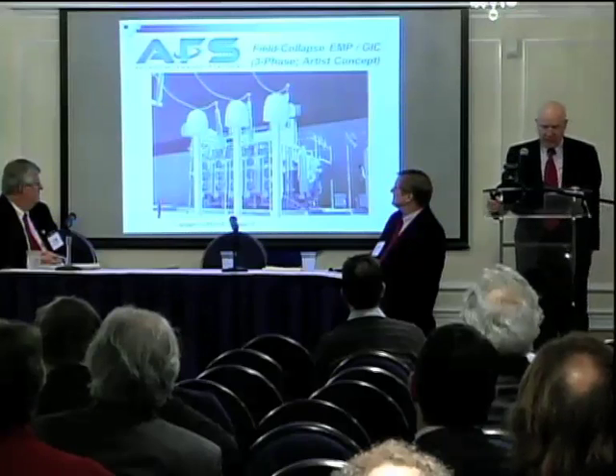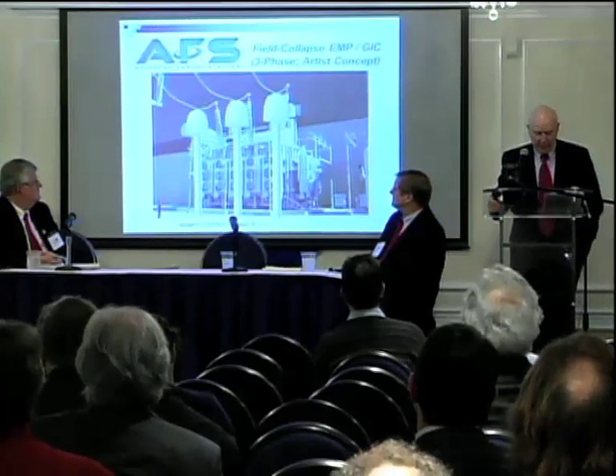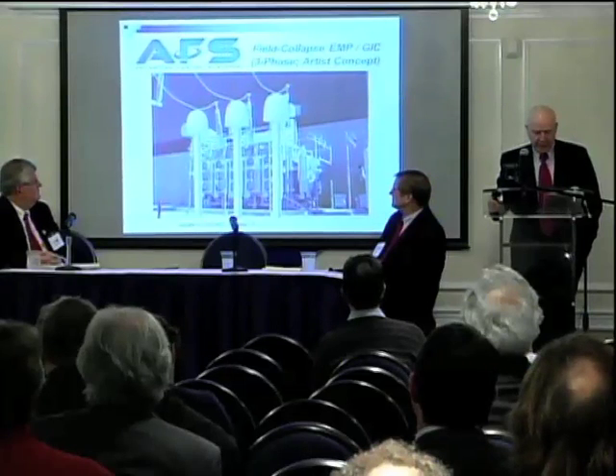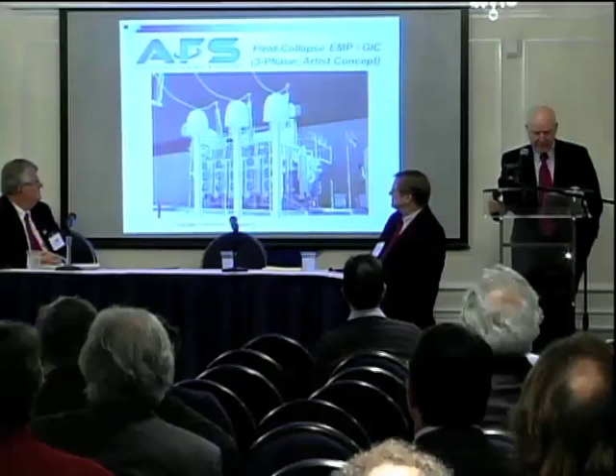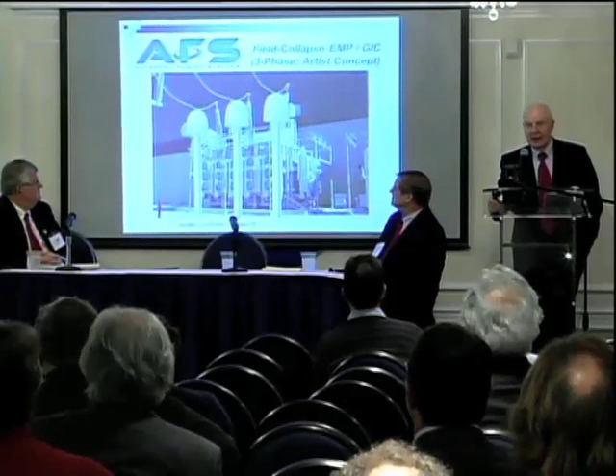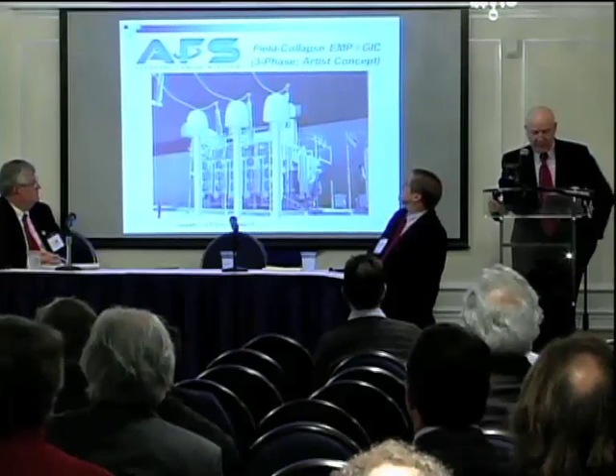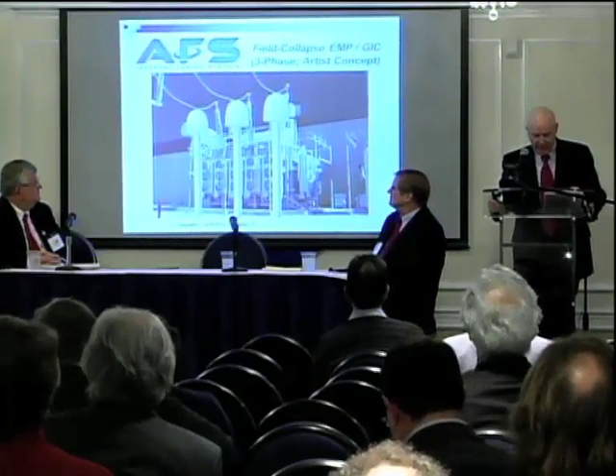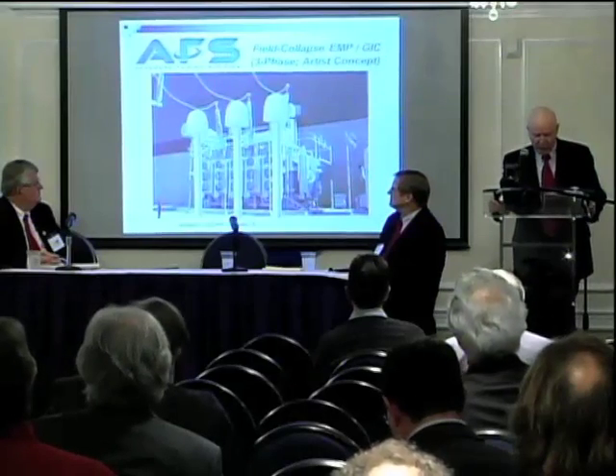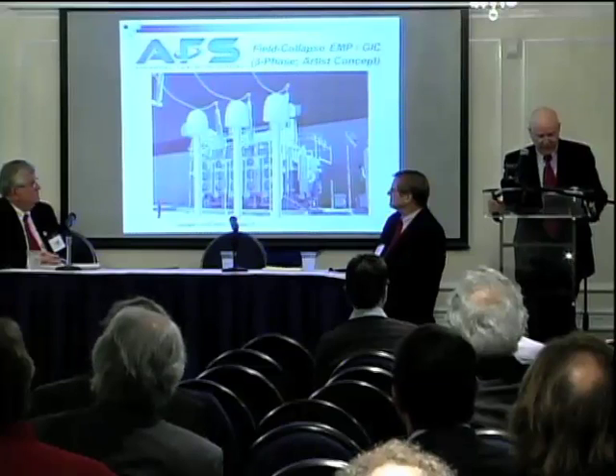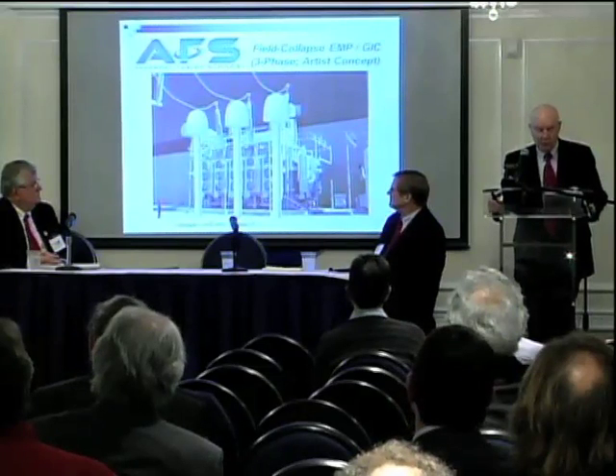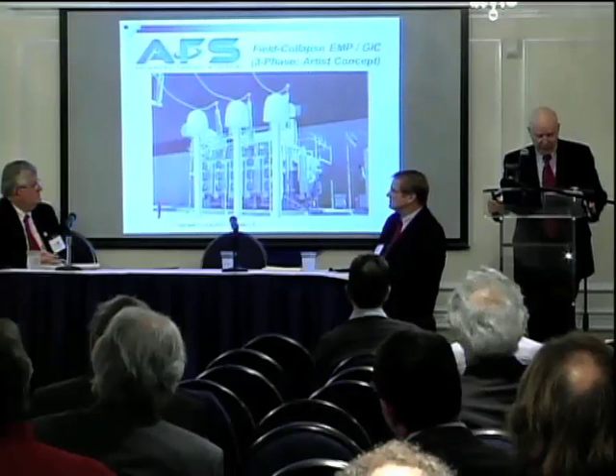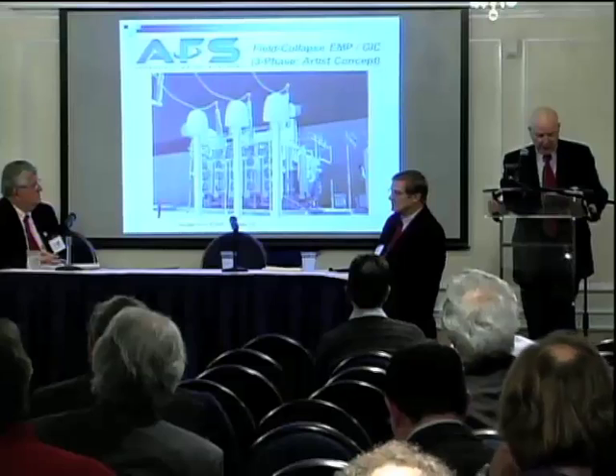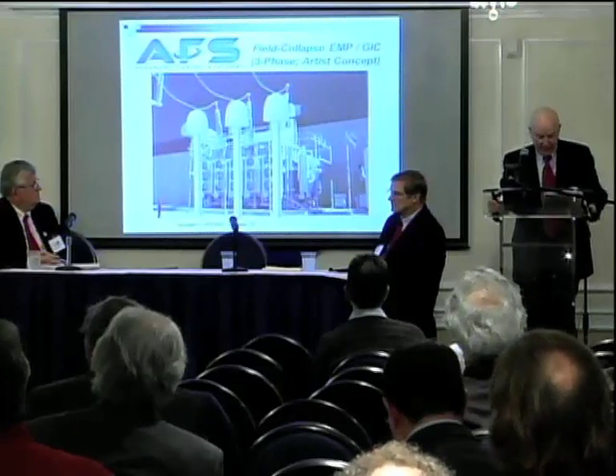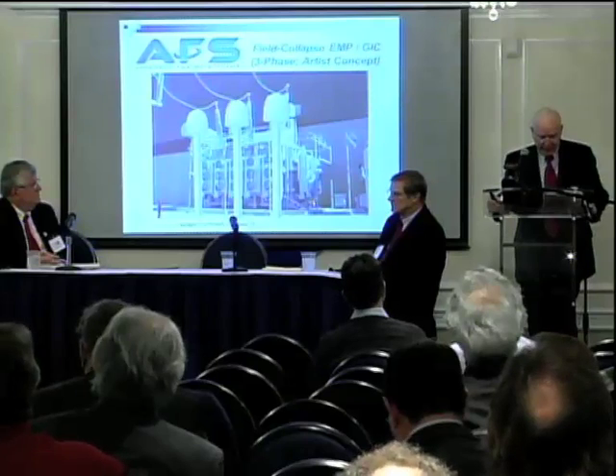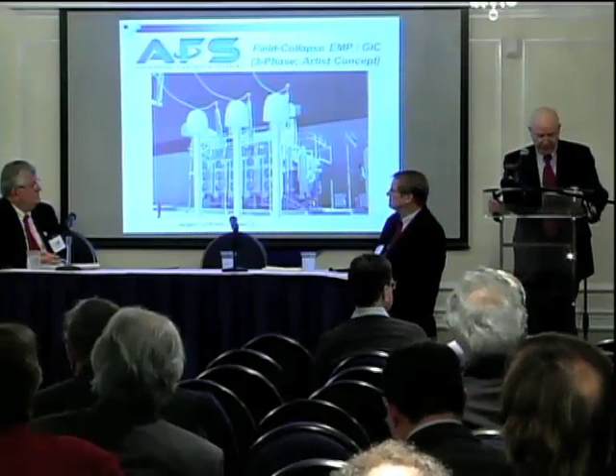This is an artist's concept of a transformer protected from both EMP and GIC with an AFS system. Each device senses the pulse coming down the line and connects to ground through a low impedance connection. The device implements field collapse protocol. Detection and operation are autonomous. The device provides hardened data output containing information on the system status and an EMP event alert.